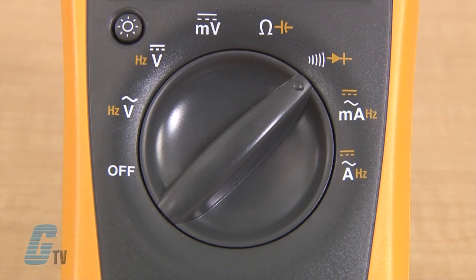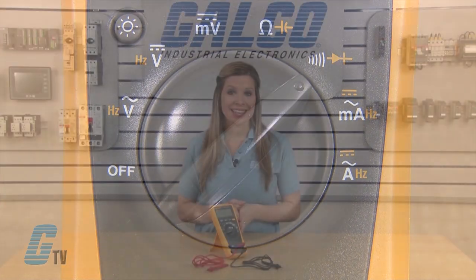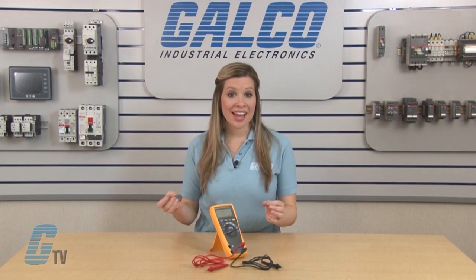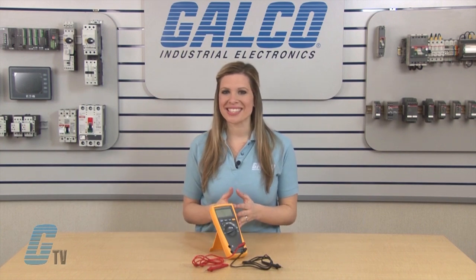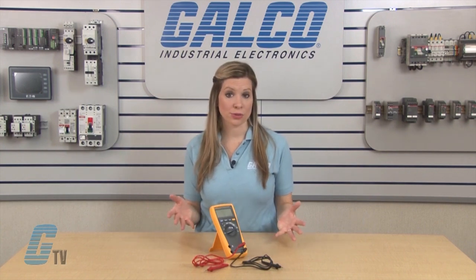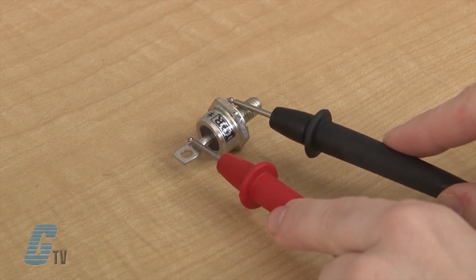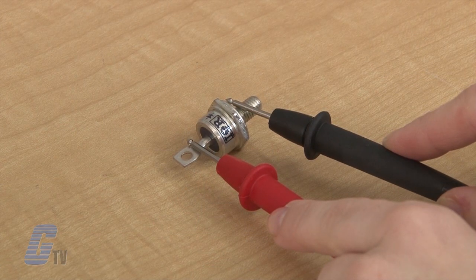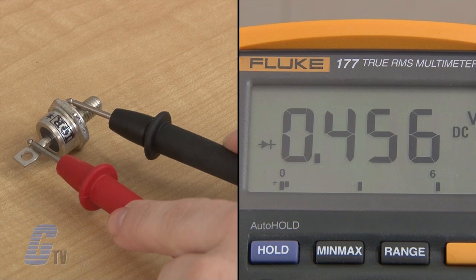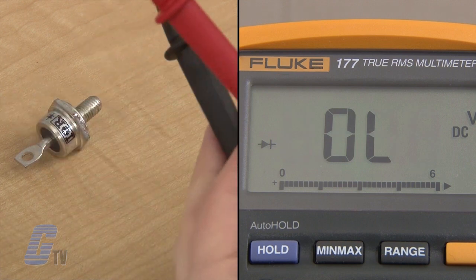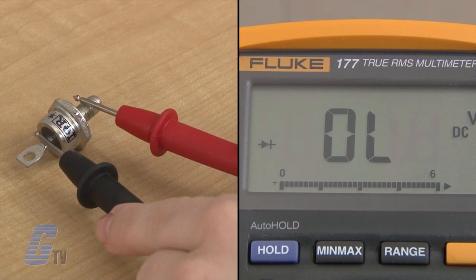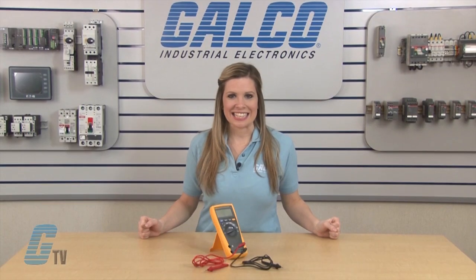Diode testing is displayed by a diode symbol. Testing a diode requires finding the anode and cathode of the diode and ensuring that the diode is disconnected from a power source. I can then use the red probe on the anode and the black probe on the cathode. There should be a voltage drop displayed and a numerical value on the display. I will then reverse the probes and conduct the test again. There should be no voltage drop, and an OL should display. This indicates the diode is working properly, with voltage going in one direction and not the other.